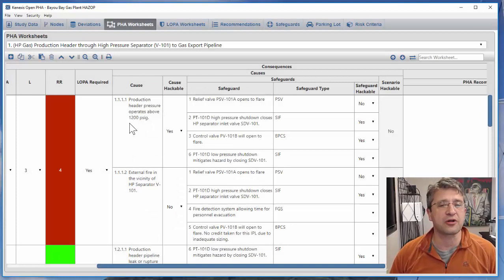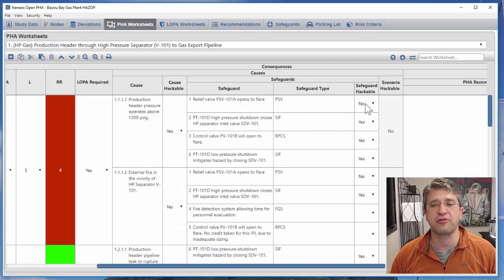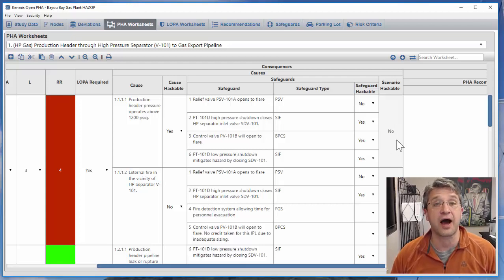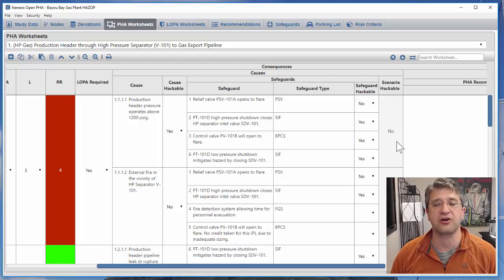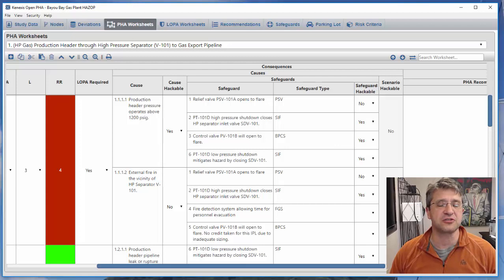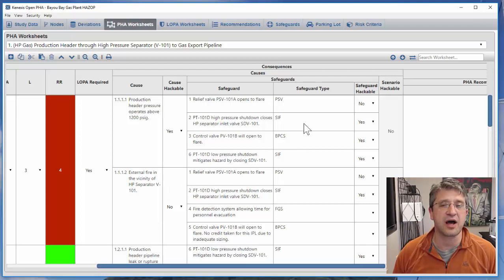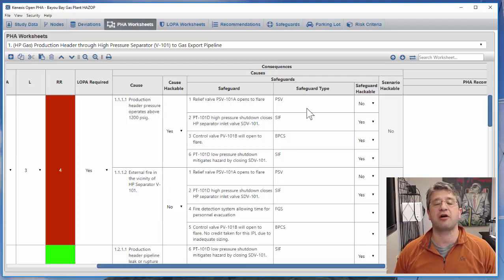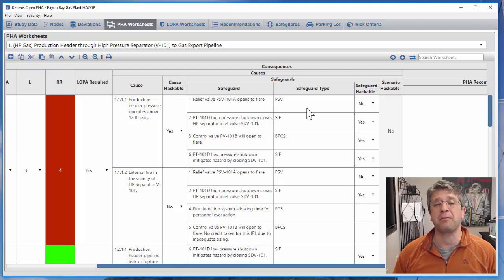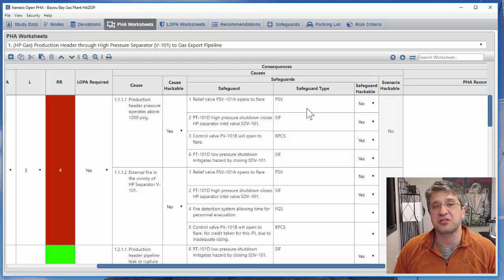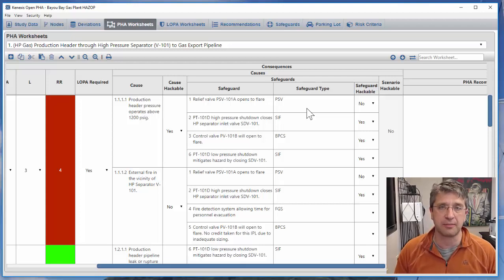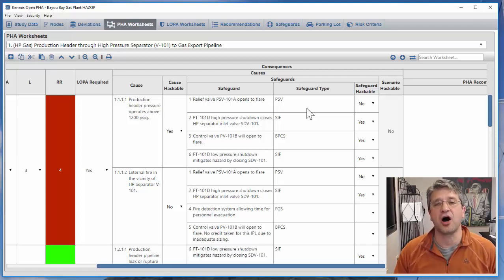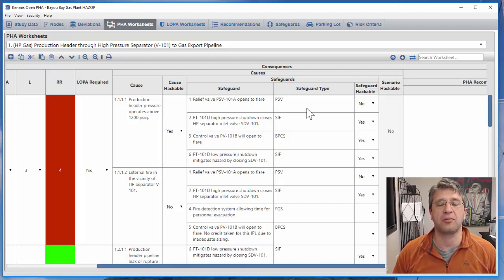When you go through all the causes and determine whether they're hackable, and go through all the safeguards and determine whether they're hackable, the logic makes the calculation as to whether or not the entire scenario is hackable. In this example for the first two safety functions, the scenarios are not hackable either because the cause was not hackable or there's at least one safeguard that's not hackable. You're going to find that for the great preponderance of PHA scenarios, maybe greater than 90 to 95 percent, the scenarios are not hackable by cyber attack. That means you can focus your cyber security resources against other scenarios that might be hackable.